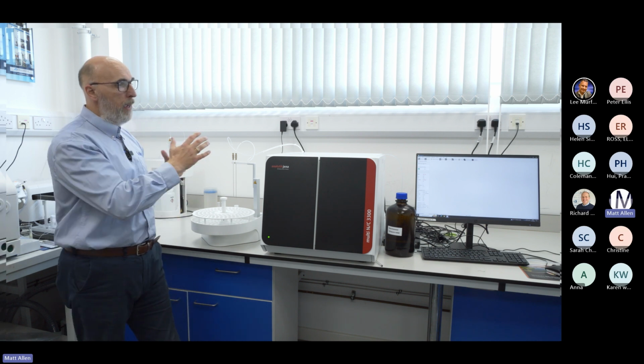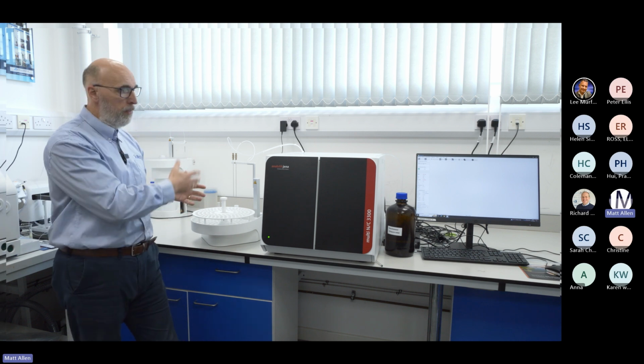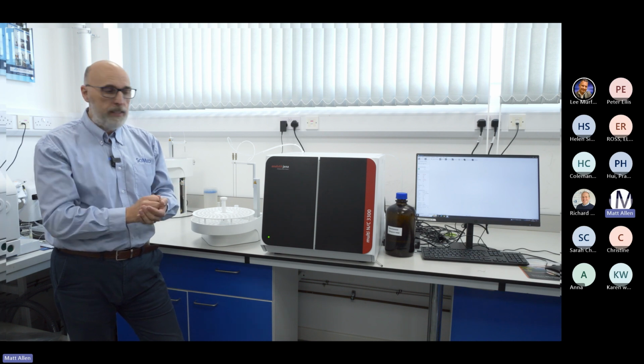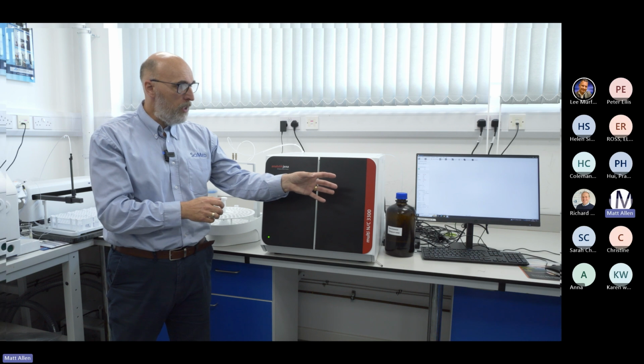And obviously what we've talked about here is liquid analysis, liquid autosampler injecting. We have options for solids analysis. There's something called the HT1300, which is a pretty manual way of putting a sample into a ceramic boat. We're combusting it, and then the CO2 is carried across and uses the detector, which is in one of the multi N/C units. You can automate that by adding an autosampler to it if you so wish.